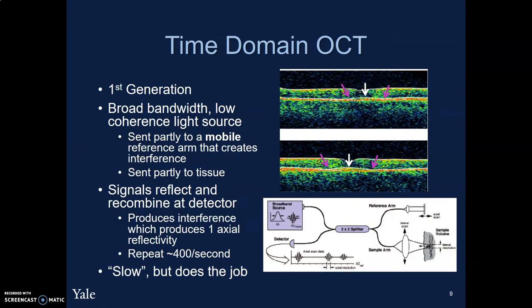The first generation of OCT was time domain OCT. This used a broad-bandwidth, low-coherence light source sent over to a mobile reference arm that created interference. The name comes into play in that the OCT is based off interferences generated via time as the reference arm moves through. The signals reflect and recombine back at the detector, which uses the interference patterns to generate axial scans. Because it's time-dependent, it's relatively slow, doing about 400 scans per second, but it does reliably generate accurate pictures.